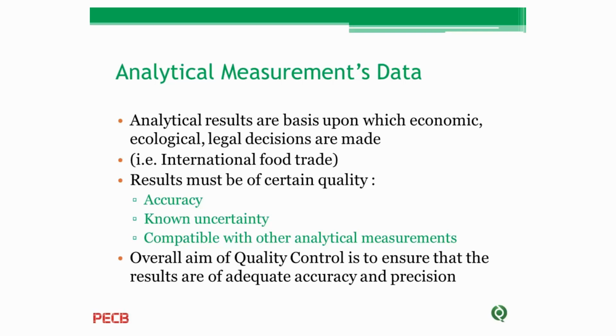It means that in an accredited laboratory, when we report the result, it is not technically right, from the metrological point of view, to report only one number. We should inform our customers, the laboratory users of the results, with an interval that we believe the true value will be in that interval.